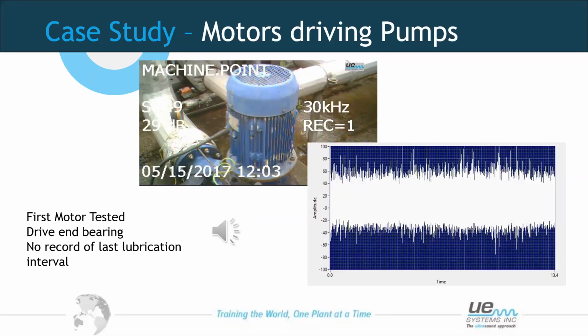So another couple of questions coming in at the moment. The squeaking sound, what was the squeaking sound? That is the metal on metal sound that we're picking up there, a very severe lack of lubrication, which is causing damage to the bearing. And also things like impeller wear or wear on the rings.